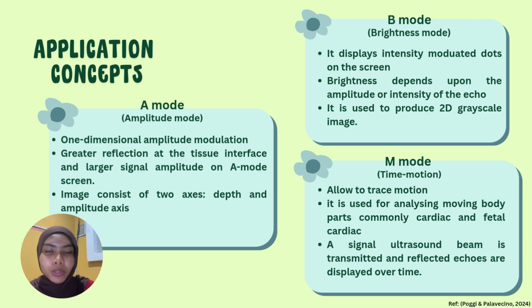Next, B mode stands for brightness mode. In this mode, the echoes are displayed as dots on the screen. The brightness of each dot depends on the intensity of the reflected echoes. Stronger echoes appear brighter and weaker echoes appear darker. B mode is used to produce 2D grayscale images and is the most common mode used in medical ultrasound today.